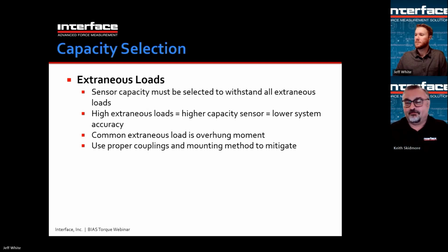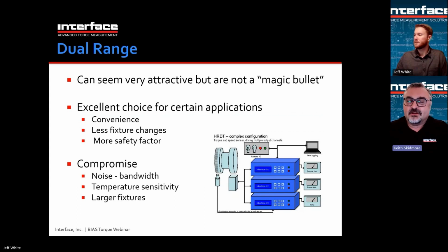Moving on. So this is an example, dual range sensors. We have our model T6 and T7. ATQ can be had in a dual range configuration. This shows our older HRDT. We sold a lot of those with dual or even triple range configurations. But just keep in mind, it's not a magic bullet. There's no magic to a dual range. It's not like you have a mechanically overload protected low range. Typically, it's the same range sensor, but with extra magnification or amplification on the low range signal.